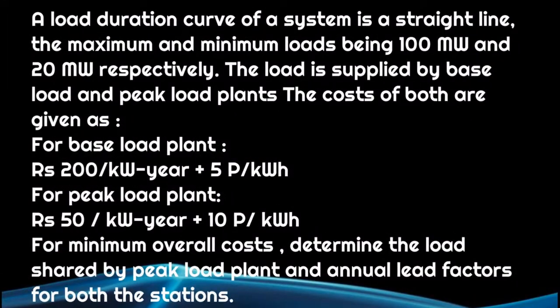Now first I will read the given question. A load duration curve of a system is a straight line. The maximum and minimum load being 100 megawatt and 20 megawatt respectively. The load is supplied by base load and peak load plants. The cost of both are given as: for base load plant, Rs. 200 per kilowatt year plus 5 paise per kilowatt hour. For peak load plant, Rs. 50 per kilowatt year plus 10 paise per kilowatt hour. For minimum overall cost, determine the load shared by the peak load plant and annual load factors for both stations.